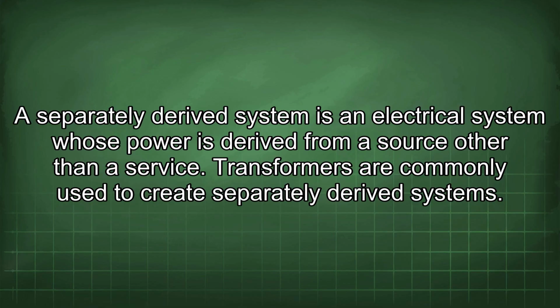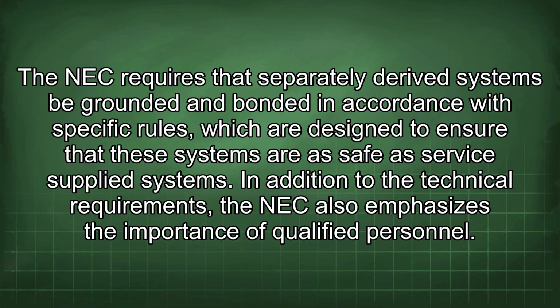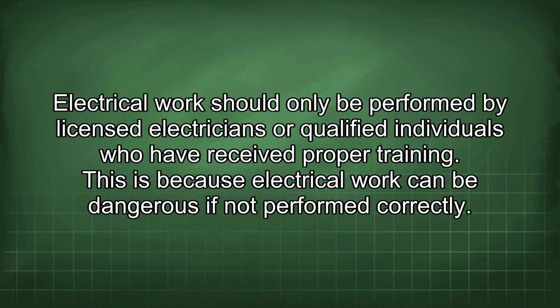Transformers are commonly used to create separately derived systems. The NEC requires that separately derived systems be grounded and bonded in accordance with specific rules, which are designed to ensure that these systems are as safe as service-supplied systems. In addition to the technical requirements, the NEC also emphasizes the importance of qualified personnel. Electrical work should only be performed by licensed electricians or qualified individuals who have received proper training. This is because electrical work can be dangerous if not performed correctly.